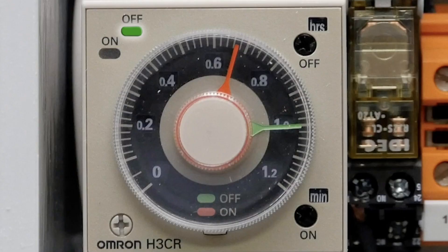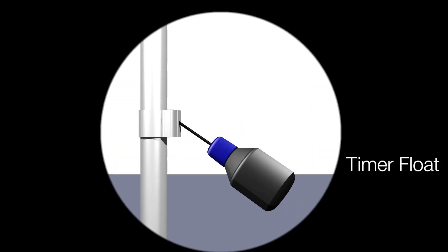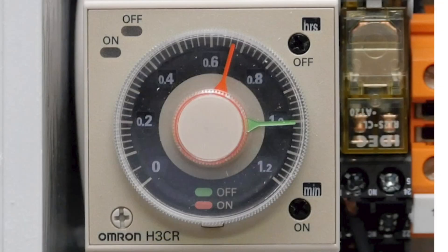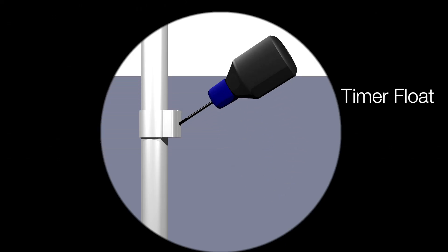After the pump off cycle has elapsed, the timer will engage the pump and go through the pump on cycle. When this cycle is complete and if the timer float is in the down position, the pump will shut off. If the timer float remains in the up position, the pump off cycle will begin again.